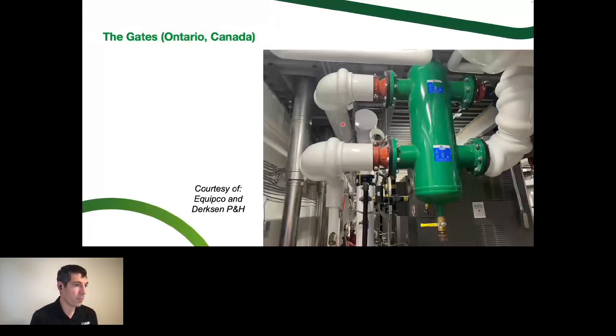This is another example. Three big commercial boilers, like 1.5 million BTU boilers with the hydro separator above here. If you were going to do closely spaced tees at this size, you're going to have to spend a week welding that, and you would need three times the amount of space, which could be a drag in a mechanical room like this. So this is kind of nicely tucked up into the vertical space next to the boiler there, and is a good example of a commercial separator in this scenario.